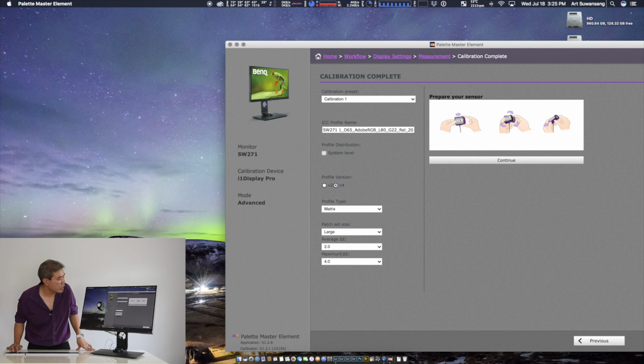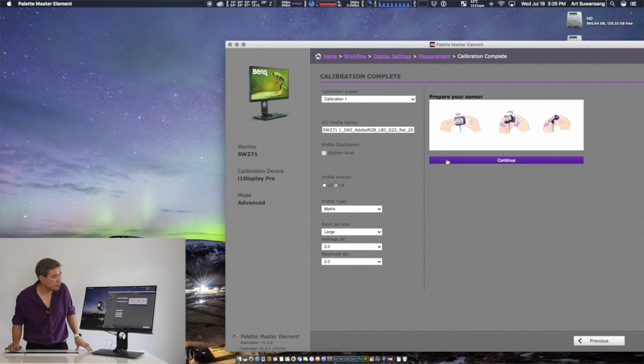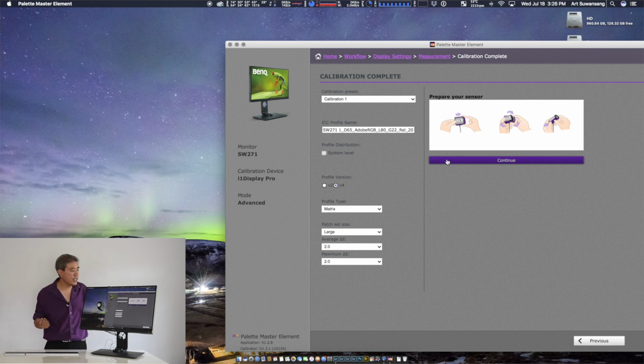Patch set, we're going to do large. Average delta E we'll set to 2, maximum delta E to 4. In fact, let's change that so that maximum delta E is 2, and we'll set both of them to 2. Technically, the average delta E should be below 1 in this case, so we'll see if our calibration was good. I'll go ahead and click continue.